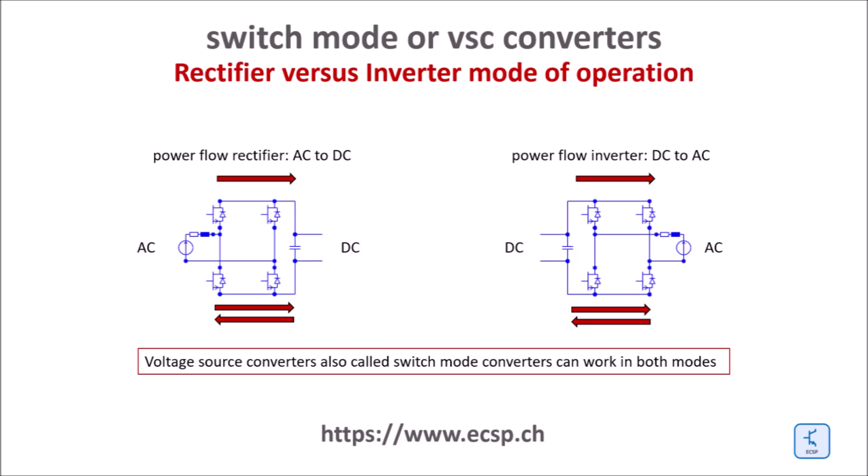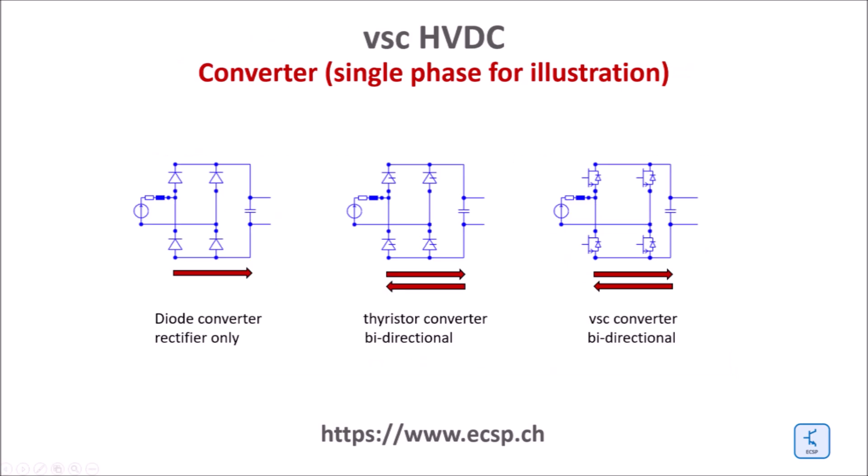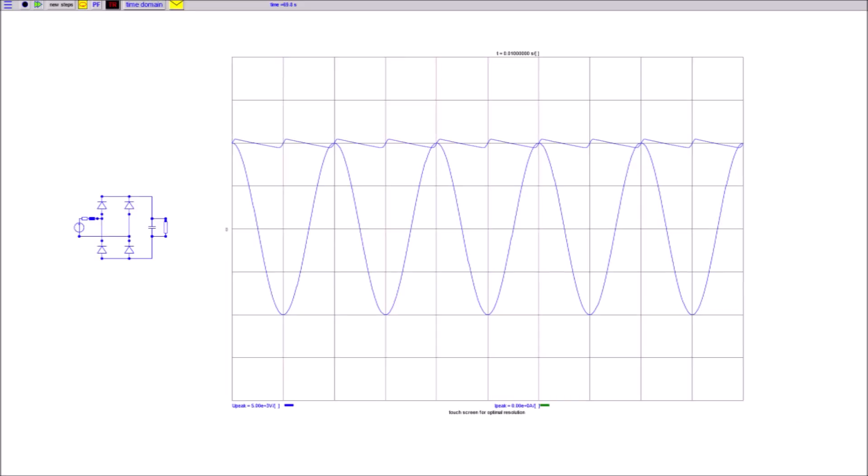Note that switch mode converters can work in both directions — in rectifier as well as in inverter mode. There are three basic families of converters: diode converters work as rectifiers only. Thyristor converters and voltage source converters or switch mode converters can be operated as controlled rectifiers or controlled inverters. Thyristor converters have been explained in great detail in the video about conventional HVDC.